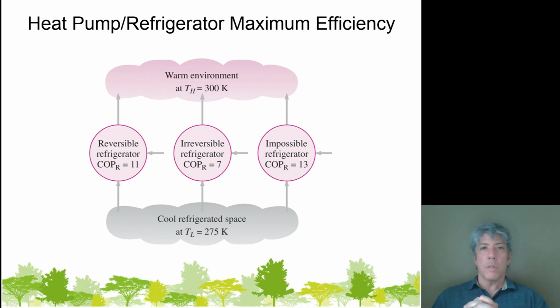And what ends up happening is the air coming out of the register doesn't feel all that warm to the occupants, and so that's where heat pumps got a bad reputation initially when they were introduced, because the air coming out of the register felt kind of cold. As a matter of fact, if you put your hands over it, it does feel cold, because you would have water on the surface of your skin, and that water would be evaporated off and feel like it's actually cold air coming out of it, when in fact it's warmer than the average temperature of the home. And the purpose, of course, for having that just mediocre warm temperature air coming out of the register is so that you're working between a smaller temperature range and therefore have higher efficiency, which is the whole point of having a heat pump in the first place.